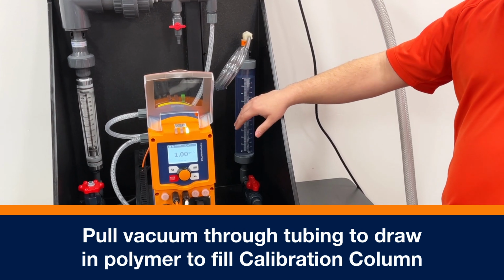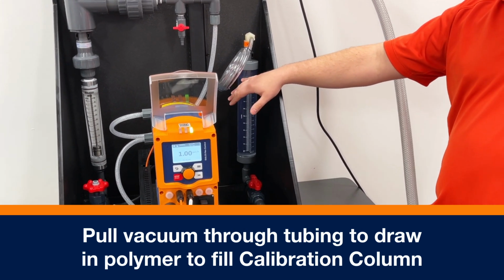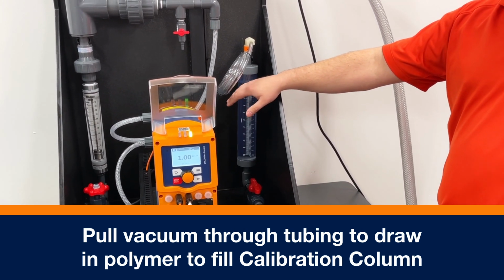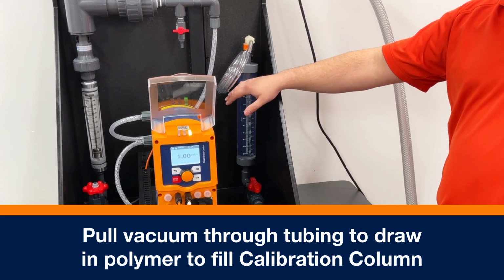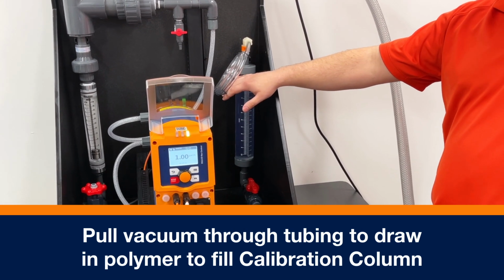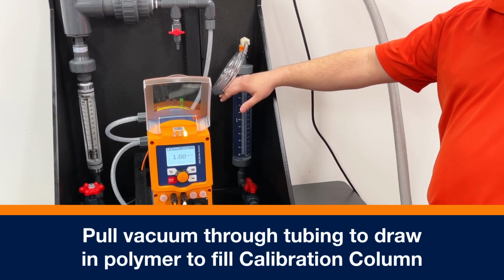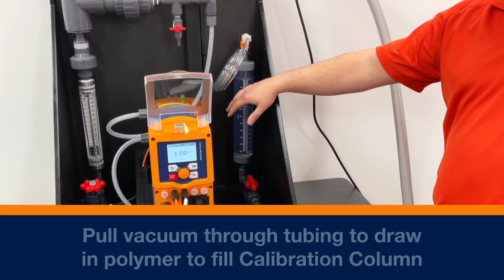calibration column. If for whatever reason you need to flush this calibration column, you will not use water. Never use water in this calibration column. It should only have mineral oil or polymer brought into this calibration column.